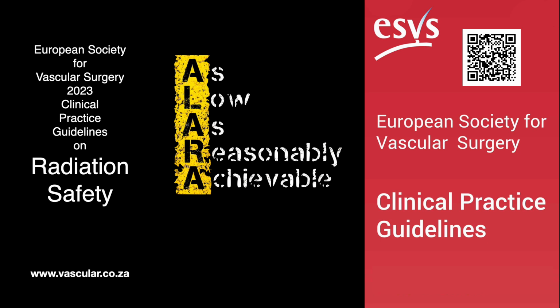Next technique, collimation. Collimation is your friend. It means using the adjustable metallic shutters or apertures within the X-ray source housing to shape the beam and restrict it to the smallest necessary field of view, just the area you need to see. Like putting blinders on the beam, what are the benefits? Two main benefits. First, it directly reduces the volume of patient tissue being irradiated, which lowers the patient's overall dose, specifically the CAK-PSD. Second, by reducing the irradiated volume, it reduces the amount of scatter radiation produced. And scatter is the main source of dose for staff. Exactly. The reduction in scatter is generally proportional to the reduction in the beam area. The guidelines mention a figure showing KAP reduced from 42 to 14 Gy·cm² for Sensis 1. Just by collimating, that's a huge saving.